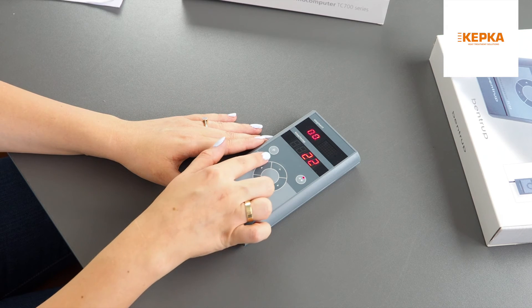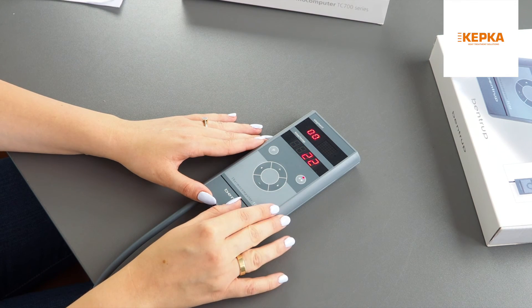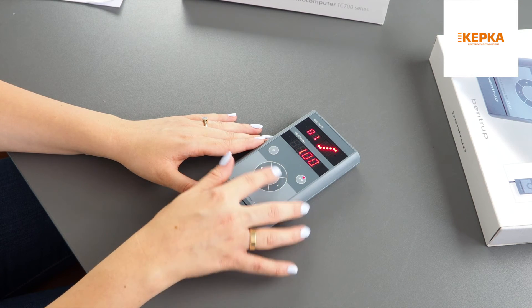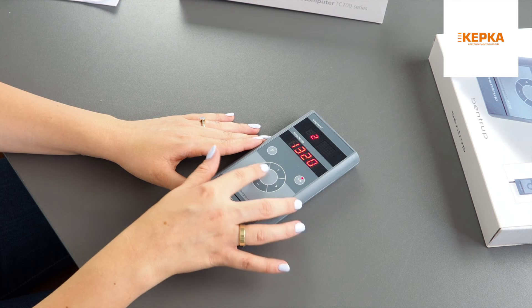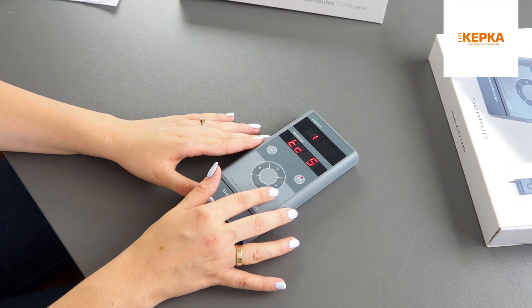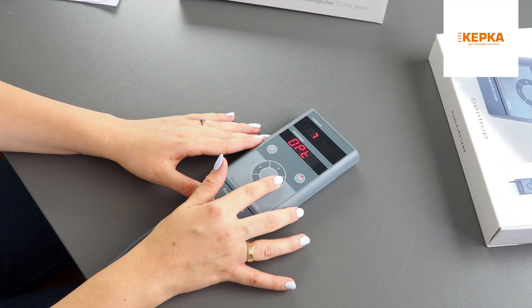If you want to go to service settings, press and hold the P button for 3 seconds. The first setting you can adjust is thermocouple. The second is maximum temperature. The third, fourth, and fifth are PID. The sixth is derivative time. The seventh is control supervisory.